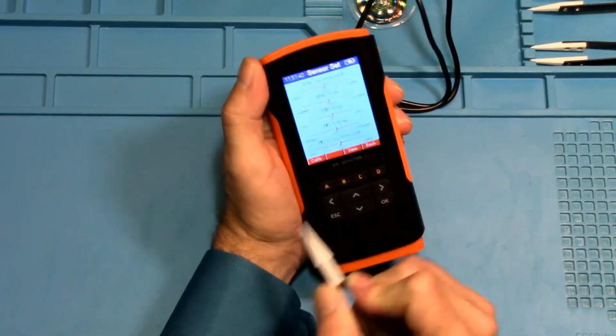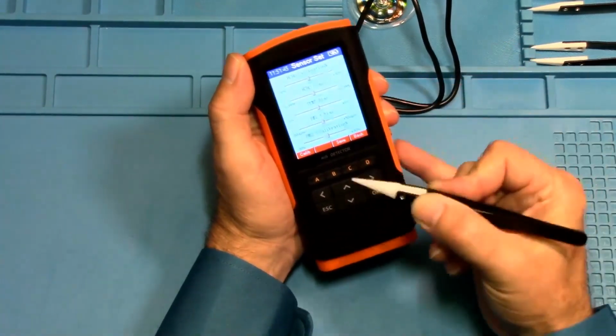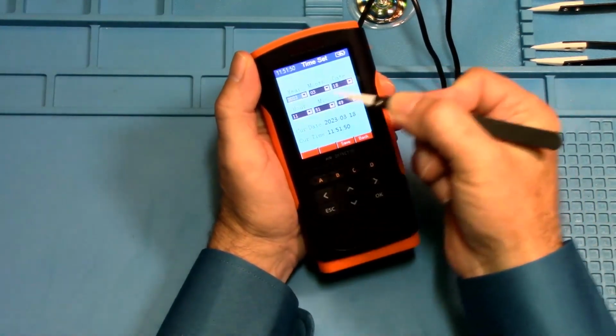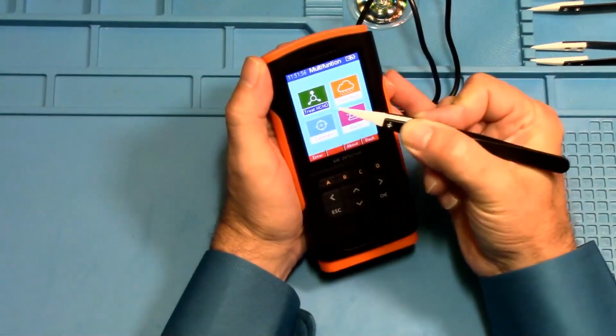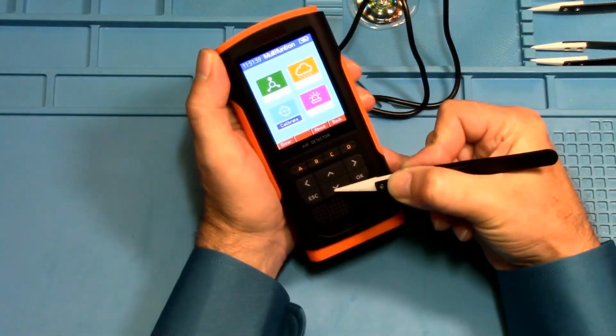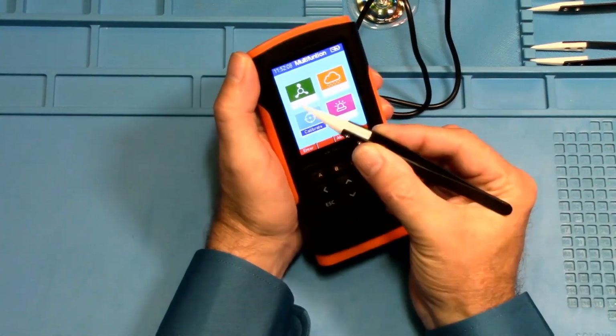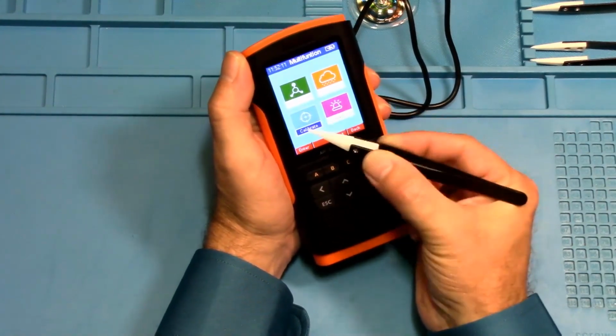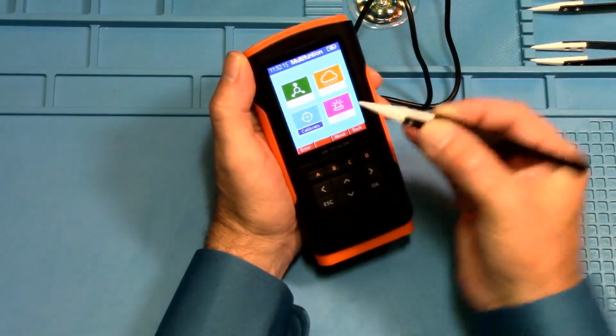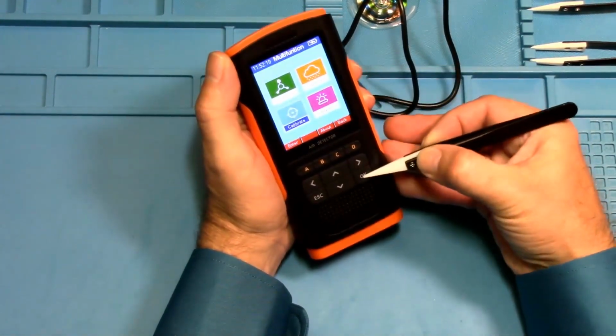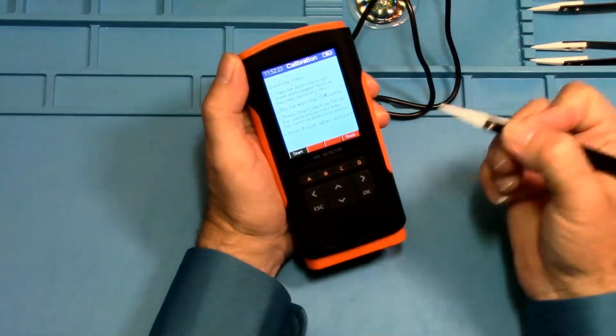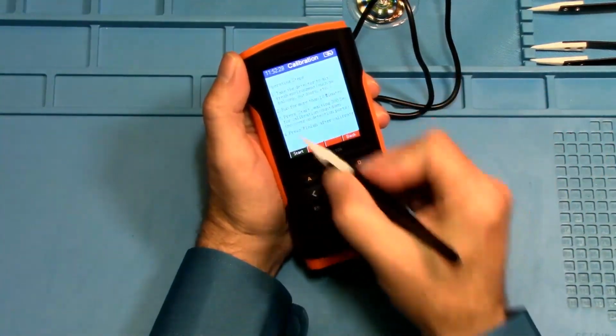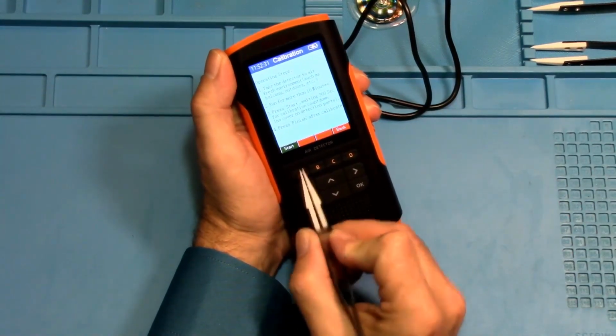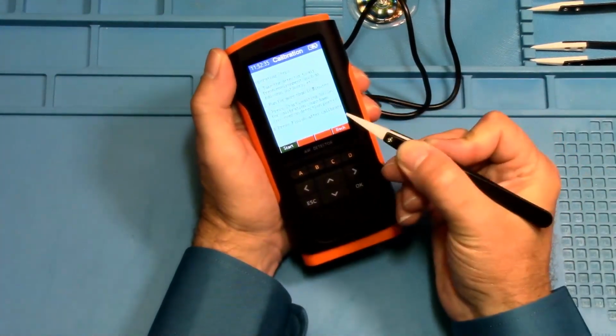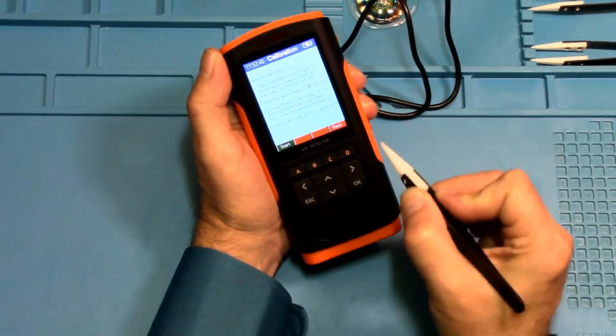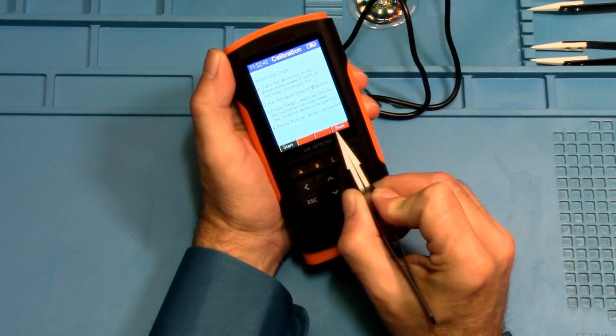Now there's other options on this screen. A for sensor. This is where you can calibrate this. Let's come back to that. Time, you can go in and set the date and time. Multiple, you can go into here, select. This information is in the manual that comes with this. I haven't really had a chance to go into this. This is also a calibrate. If you highlight this and press OK, then it does the same thing as going through from the other option. It just brings you up to the calibration screen. Then you press the A to start the calibration. Put it outside in fresh air for the 300 seconds, which is 5 minutes. And then this back option will turn into, say, finish.